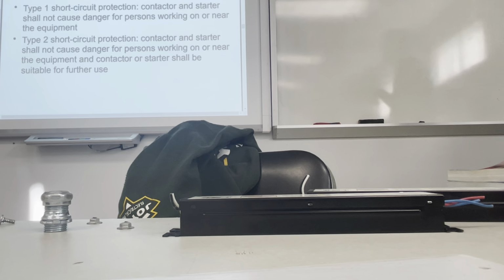Type 1 and Type 2 coordination. Type 1 short circuit protection: the contactor and starter shall not cause danger for persons working on or near the equipment. Type 2 short circuit protection: the contactor and starter shall not cause danger for persons working on or near the equipment, and the contactor or starter shall be suitable for further use.